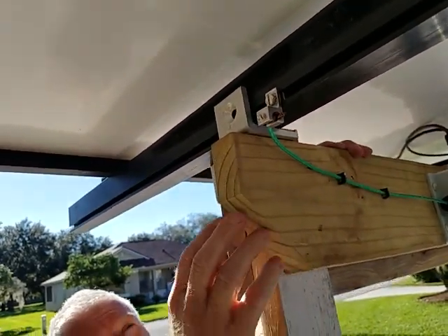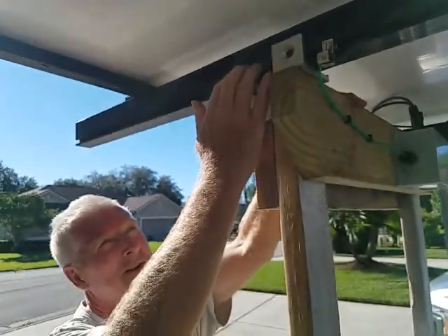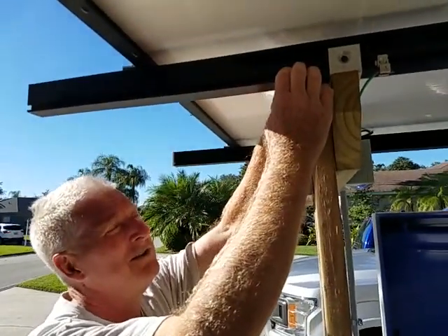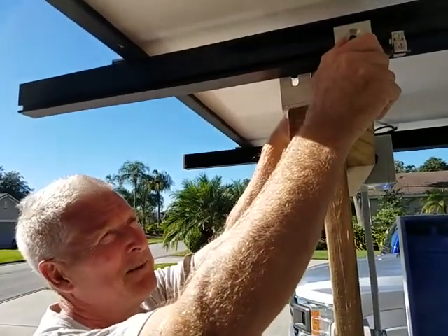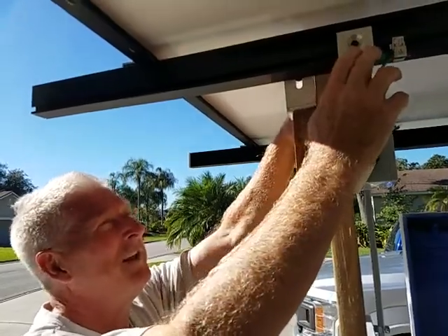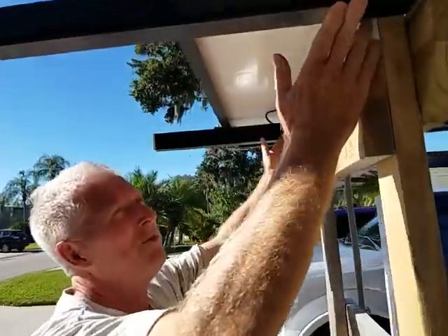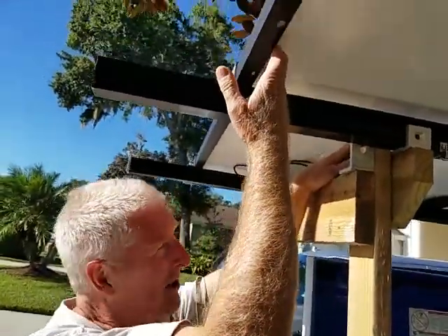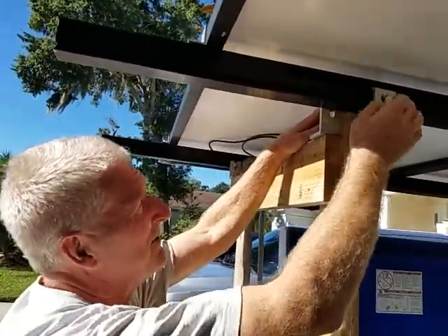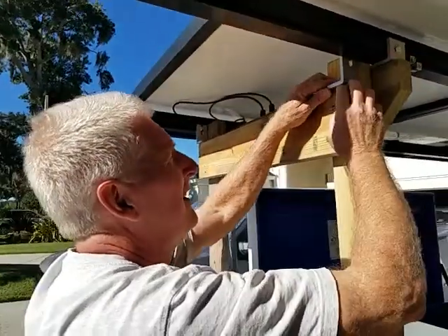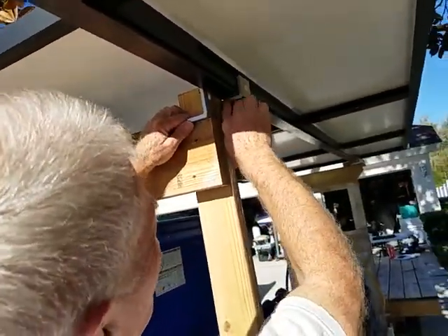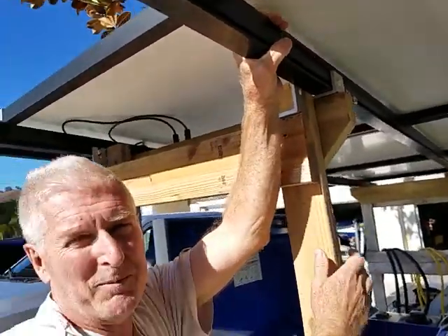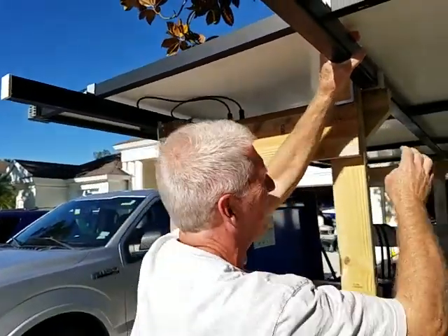So step one was create a plate underneath that provided secondary support for the rail in case this bolt loosened. These T-bolts they're called, loosened, so that there was secondary support for that. But then nothing would have prevented, if we lost multiple bolts, this whole thing from sliding and falling off and then damaging our expensive generator. So then what we did is we just flipped over an L-foot, and this L-foot is drilled into this plate, and now this can't slide off anymore.